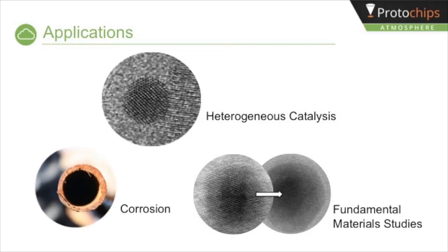Atmosphere reproduces these environments in the TEM so that specific chemical reactions can be observed and new methods developed. Thermal experiments including sintering, sublimation, and phase changes often yield spurious results when done in high vacuum, as materials can act differently when compared to atmospheric pressure conditions.